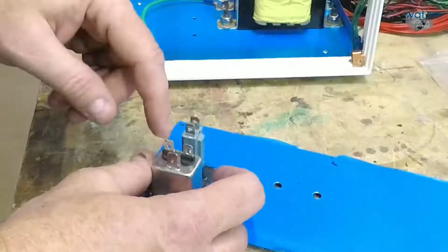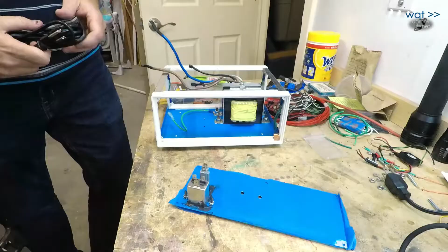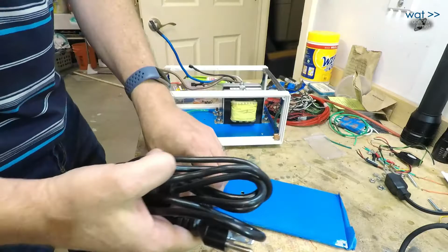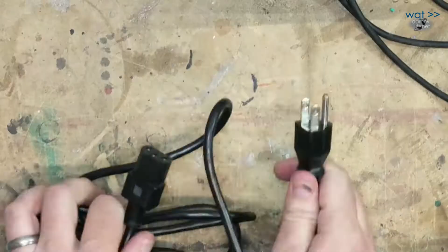Next thing we need to think about is getting a wire jumper on the back of this plate that connects the fuse to the line input on this outlet. I typically have trouble remembering which pin is line and which is neutral on an IEC power cable. For those in 240 volt countries using a 2-pole disconnect, it's not a problem, but if you have line and neutral like we do here, one side is definitely polarized. In the US, with the ground facing down, it's this pin on the right that's always line, and this one is neutral.